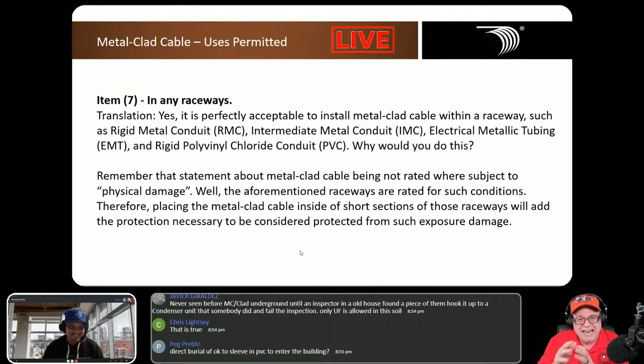I can tell you right now, you seal these raceways, you chemically seal it with PVC glue, and you make all these couplings up and everything, you're going to have water in these raceways. Even in liquid tight, you've got conductors giving off heat, so they've got what's called mutual heating from other conductors in there, and you've got an exterior ambient temperature that's different from interior ambient temperatures, which creates its own little micro atmosphere that's going to have condensation and all types of stuff in it. That goes way more than we want to talk about tonight, but that can happen. And so you're going to have moisture in there, okay?